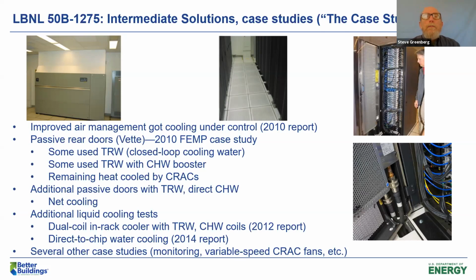We moved on from classic CRAC cooling to passive rear doors, both with closed loop cooling water just to the cooling tower with no refrigeration, and some used a chilled water booster but didn't remove 100% of the heat, so the CRACs took care of the rest. We also used passive rear doors directly with chilled water, which can provide net cooling since the chilled water is cold enough. We also did some other liquid cooling tests over the years.